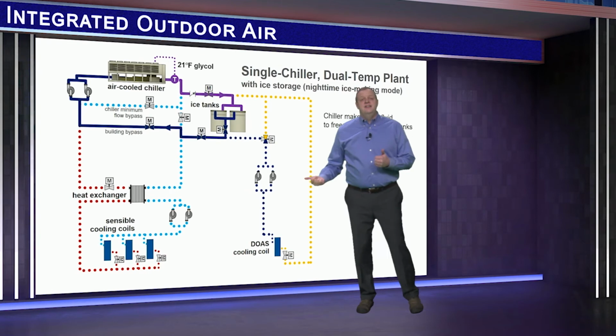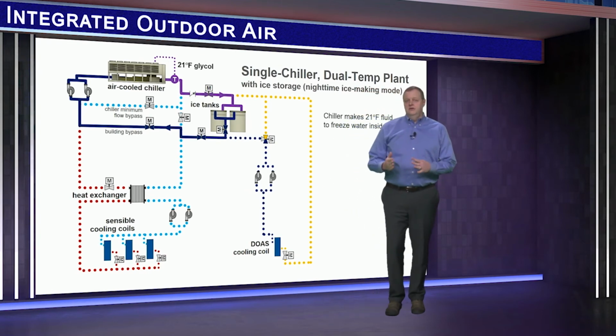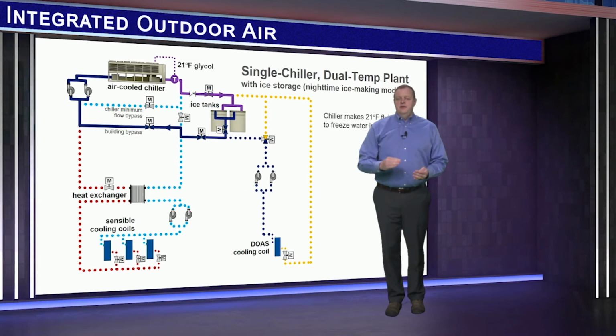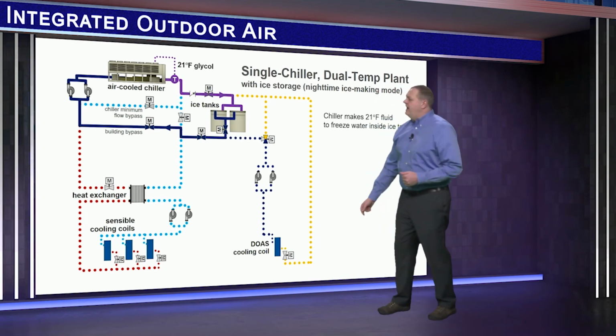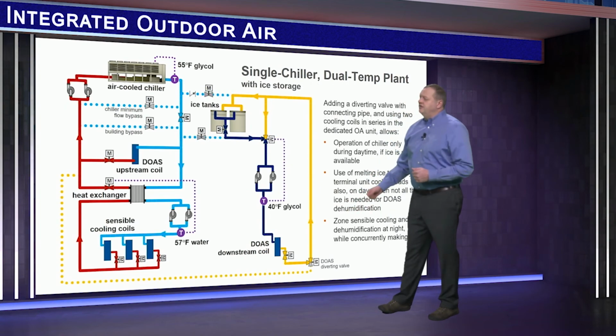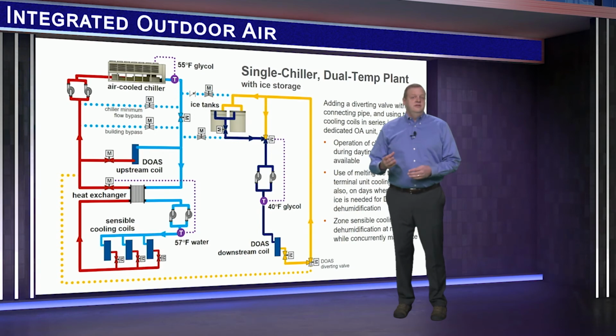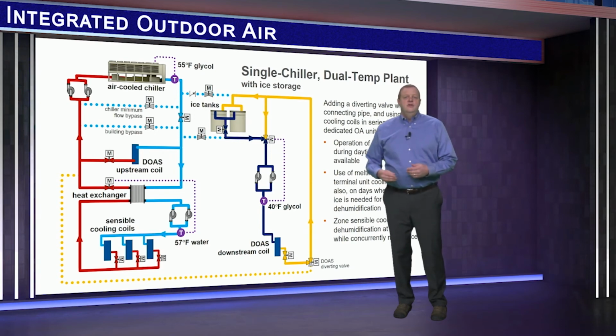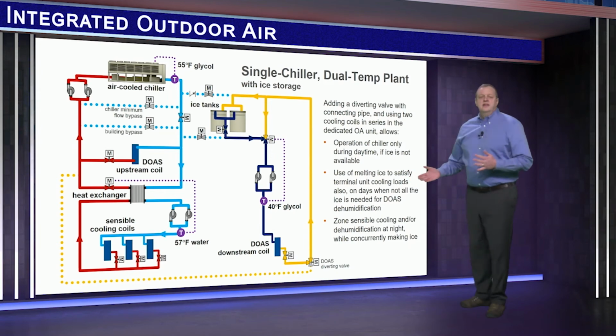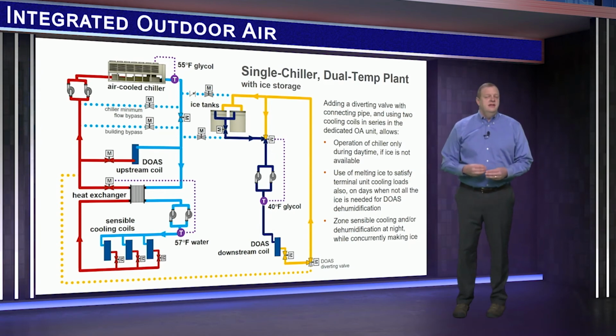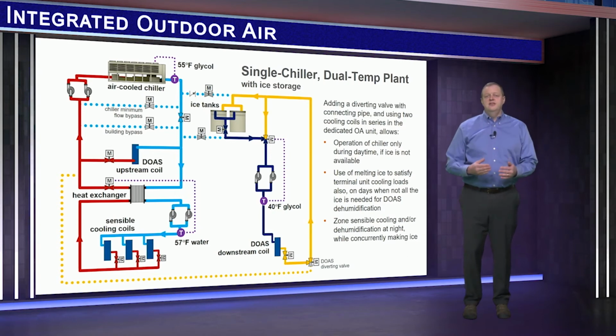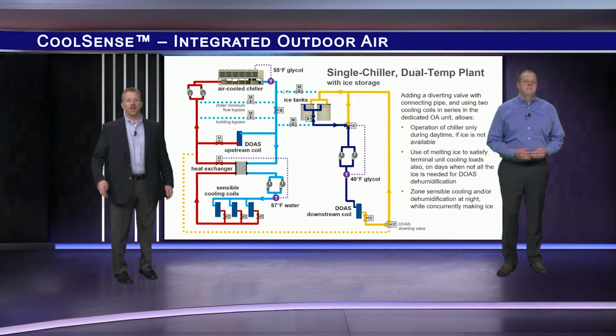Now this configuration provides the added benefit of shifting the cold water load, that's the dehumidification load from the outdoor air unit, to the nighttime hours when the cost of electricity, including demand charges, is likely to be lower. Now if you add a diverting valve and a connecting pipe, and also add a second cooling coil to the dedicated outdoor air unit like Ryan showed earlier, you can further enhance the flexibility of this configuration to operate only the chiller during daytime hours, in the event that ice is not available, for example. This also allows the plant to provide cooling or dehumidification for the building at night, while the chiller is also making ice. John, time well spent.